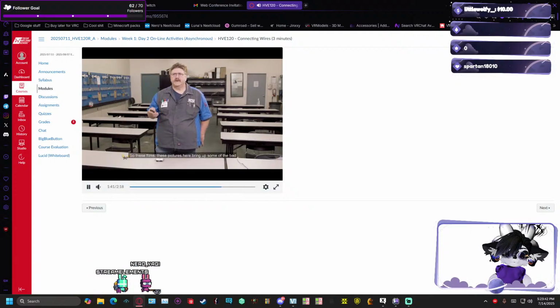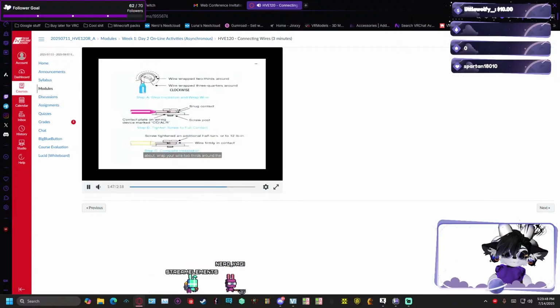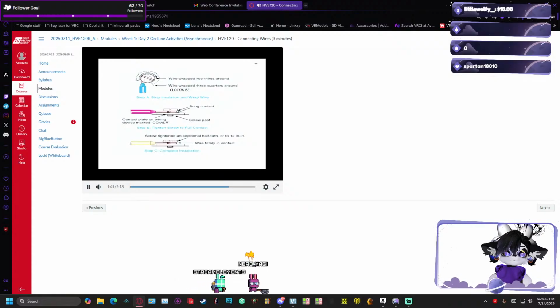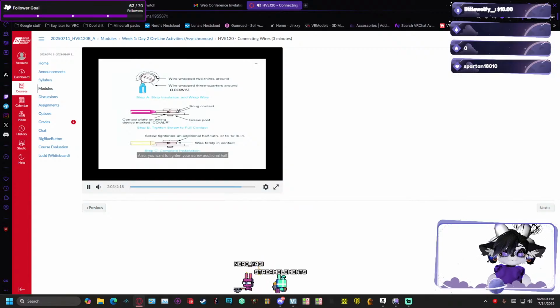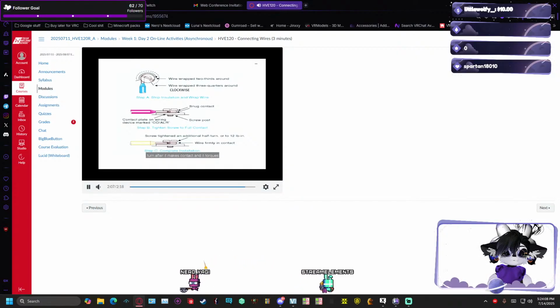So these pictures here bring up some of the bad stories if you don't follow the methods that we talked about. Wrap your wire two-thirds around the screw head. Make sure that it's a good, solid, flat connection. Make sure that you have 100% positive contact between the screw and the copper that you're putting into the device. Also, you want to tighten your screw an additional half turn after it makes contact, and it torques out at 12 inch-pounds. So you don't have to be crazy with it.